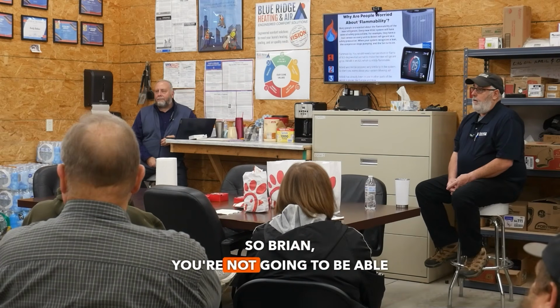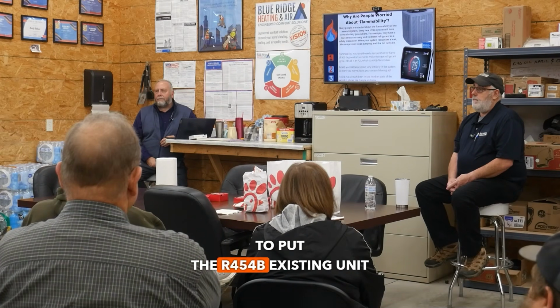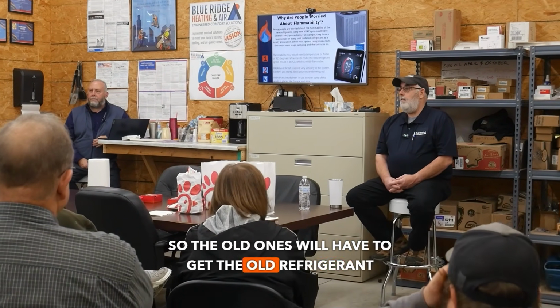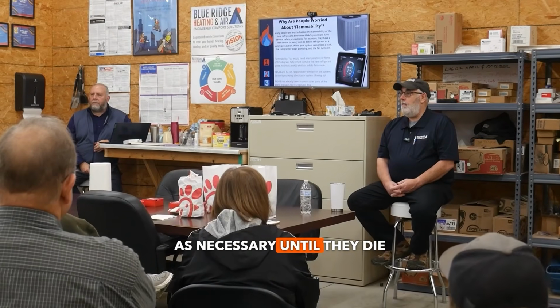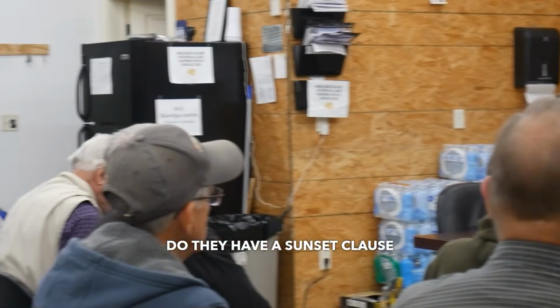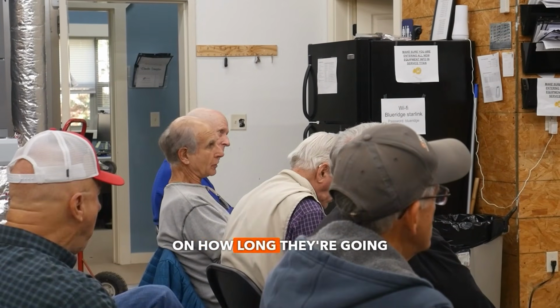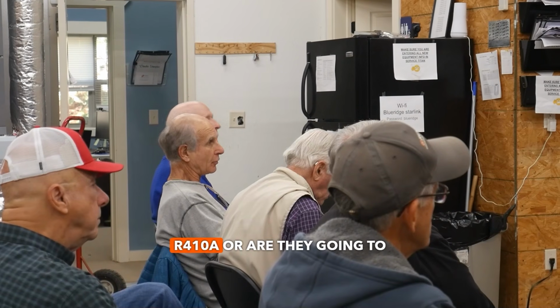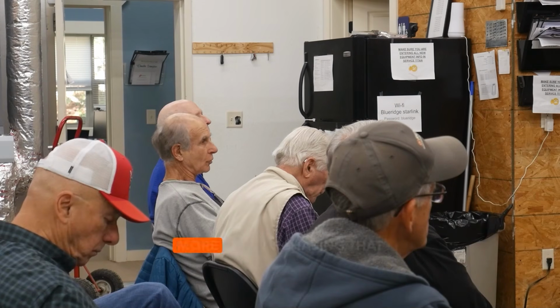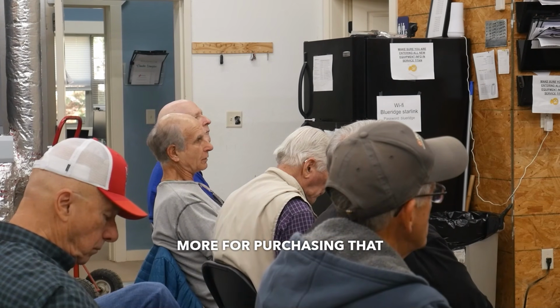So Brian, you're not going to be able to put R454B in an existing unit unless it's specifically designed for that refrigerant, right? That is correct. So the old ones will have to get the old refrigerant as necessary until they die, at which time you replace with a 454 unit. That's correct. Do they have a sunset clause or ruling now on how long they're going to produce R410A, or are they going to let the market deal with it and just keep charging people more and more for purchasing that 410A?